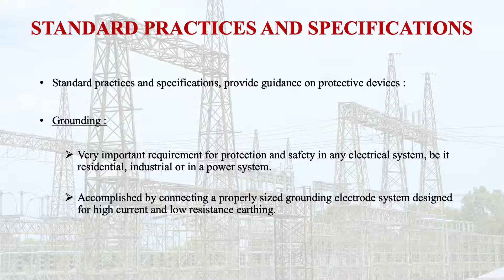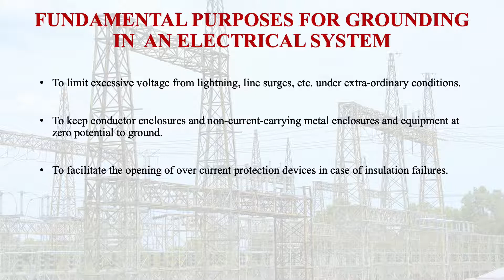Let us now discuss the fundamental purposes of grounding in an electrical system. First, to limit excessive voltage from lightning, line surges, etc. This may be in extraordinary conditions. Second, to keep the conductor enclosures and non-current carrying metal part enclosures and equipment at zero potential to ground, because any discharge or leaking of current will be dangerous. Third, to facilitate the opening of overcurrent protection devices in case of insulation failure.